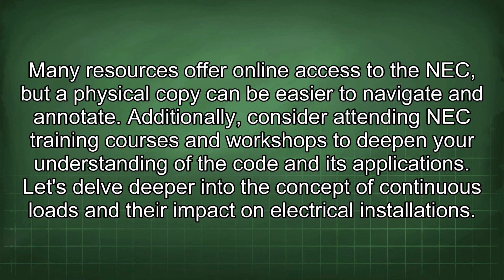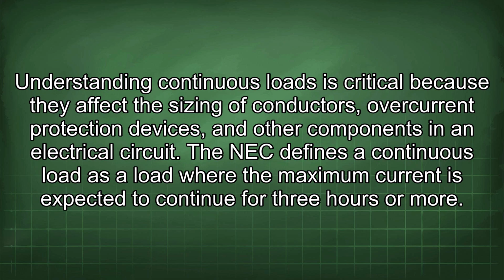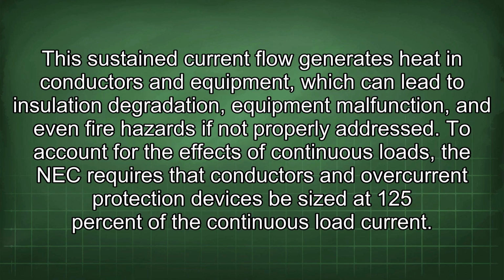Let's delve deeper into the concept of continuous loads and their impact on electrical installations. Understanding continuous loads is critical because they affect the sizing of conductors, overcurrent protection devices, and other components in an electrical circuit. The NEC defines a continuous load as a load where the maximum current is expected to continue for 3 hours or more. This sustained current flow generates heat in conductors and equipment, which can lead to insulation degradation, equipment malfunction, and even fire hazards if not properly addressed.